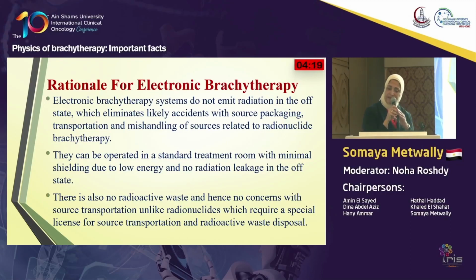They can be operated in a standard treatment room. Any room can house the device, because it is considered a mini linear accelerator. I have a mini X-ray tube placed in a low energy machine, so I don't need a specific room, I don't need a bunker, I don't need to shield.